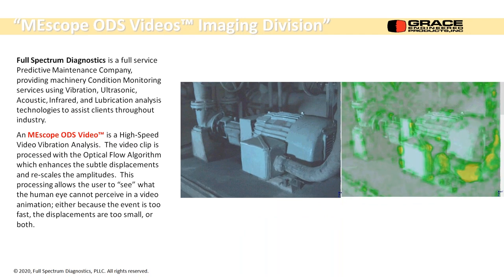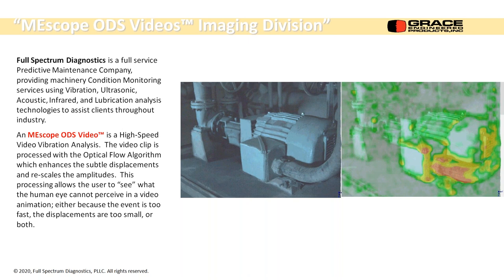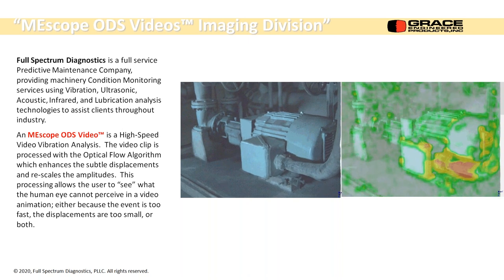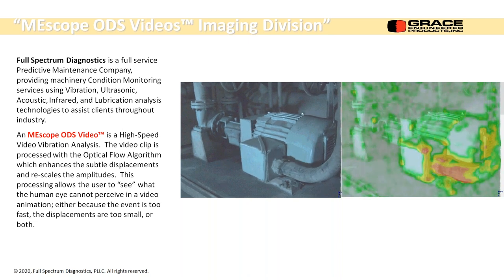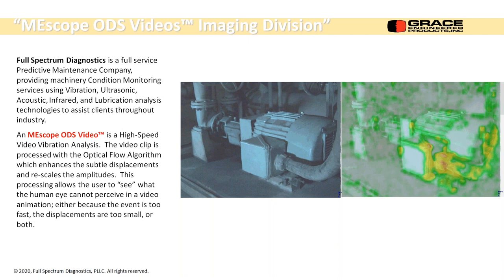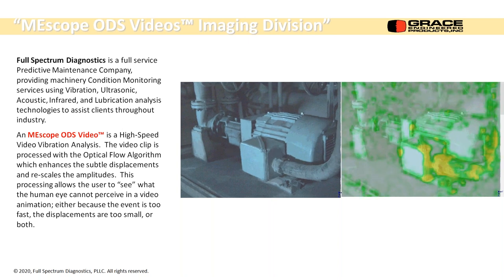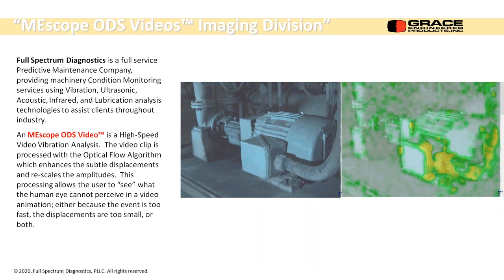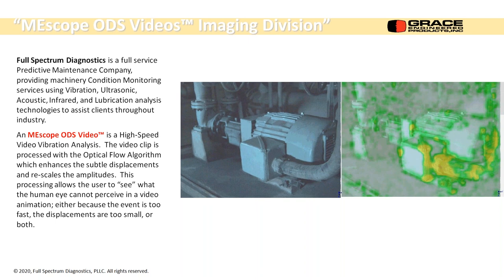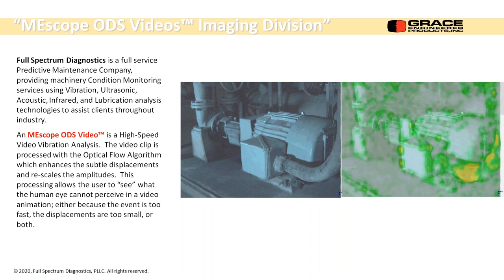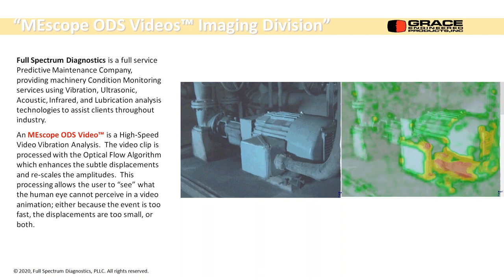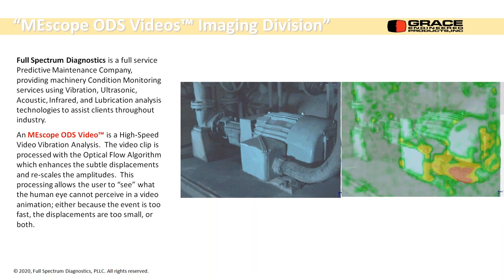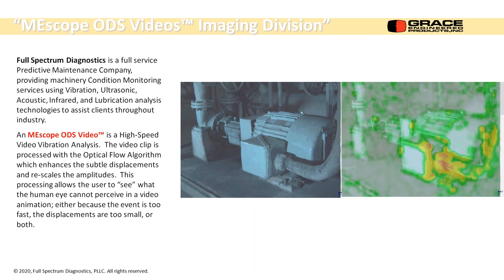We also have an imaging division. We use MEscope ODS videos. Basically, it's a high-speed video vibration analysis. We take high-speed clips, we put them through something called an optical flow algorithm, which enhances the displacements, rescales the amplitudes, and it allows us to see what the human eye can't perceive in any video animation, either because the event's too fast or the displacements are too small, or both.